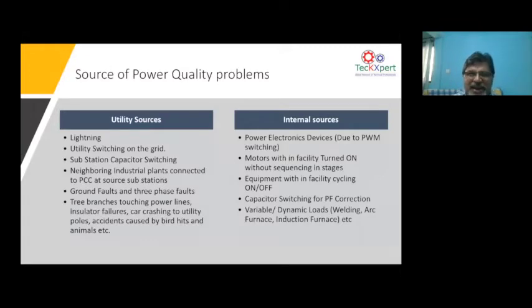All your LED lighting, your CFL, your variable frequency drives, your UPS, your servers, everything contributes to the power quality problem as an internal source. And in a factory, there will be a large motor switching on or switching off. Even in an HVAC or air conditioning system, if your large chiller motor suddenly switches on or off, you will have internally generated over voltages or a spike.